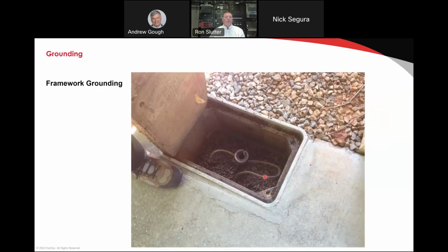Outside, we have a U in an outside ground rod. This is the ground rod here. This is a choke, so this will disrupt the flow of the current into the ground rod, and it will not work. Again, if you read a ground resistance test on this ground rod, this wouldn't matter because it's all low voltage to read that test. But if it got 100,000 amps put on it, it will not work.